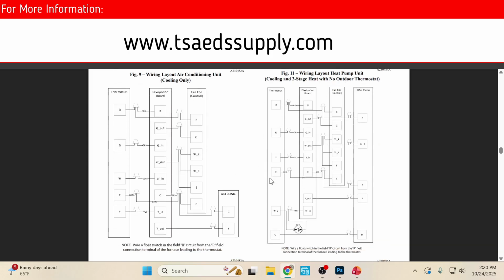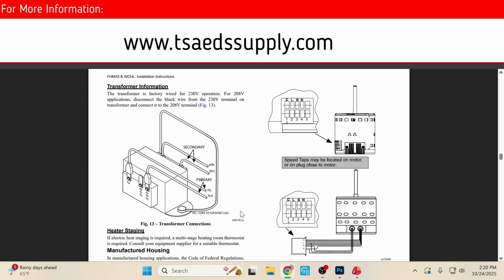So you'll look at these different layouts that you have, depending on what unit you're actually working with, and then you'll come in and you'll actually see the blower motor controls here, and you'll see these numbers quite a bit. This first one, this common, this C, that is a brown wire, and that's your common on your 24 volts. So what these new motors are is they have this wire here, the L and the N have constant hot power and a ground on this motor at all time, and it's waiting for a 24 volt call. So it's like a 24 volt call is the switch. So your blower motor is constantly got 208, 230 on it, and it's waiting for the 24 volt signal to come on.